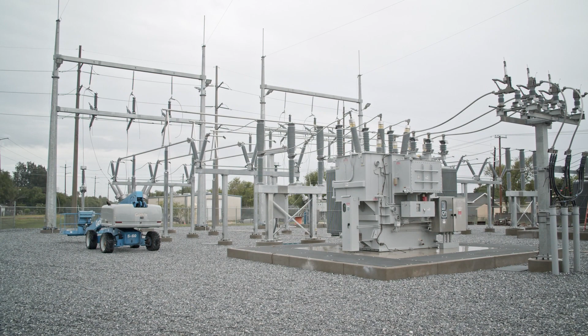The grid carries a tremendous amount of power, 138,000 volts on the bigger transmission lines, in some cases 345,000. We manage that using instrument transformers connected around the conductors, taking a really large amount of electricity and transforming it down into a smaller amount we can connect to a computer protective device to help manage the grid.